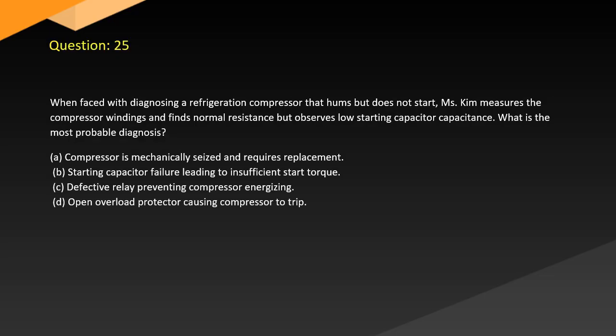Question 25. When faced with diagnosing a refrigeration compressor that hums but does not start, Kim measures the compressor windings and finds normal resistance but observes low starting capacitor capacitance. What is the most probable diagnosis? A. Compressor is mechanically seized and requires replacement. B. Starting capacitor failure leading to insufficient start torque. C. Defective relay preventing compressor energizing. D. Open overload protector causing compressor to trip.